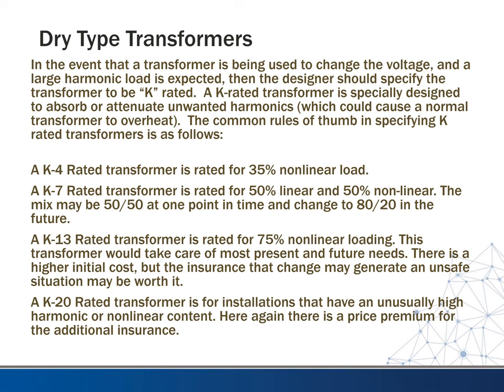So as a designer, you do need to have some knowledge of what type of load you're serving. And many times, if we know there's a large concentration of nonlinear loads, we might even run two separate feeders over there. One is noisy and one is non-noisy. And so we run all the noisy loads to one panel. So if you had a lot of computer outlets that you knew were going to be used there, and then the general purpose outlets and other linear loads, we'd run to another panel. So we'd run a K-rated transformer to one and a non-K rated transformer to the other.